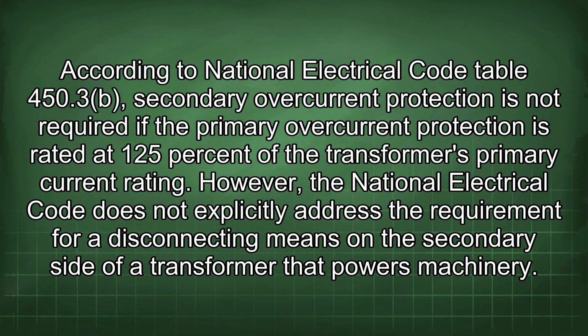According to National Electrical Code Table 450.3, secondary overcurrent protection is not required if the primary overcurrent protection is rated at 125% of the transformer's primary current rating. However, the National Electrical Code does not explicitly address the requirement for a disconnecting means on the secondary side of a transformer that powers machinery.